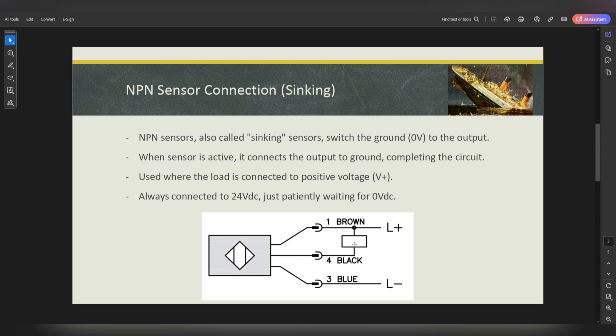When I speak about the load, it simply means the device which the sensor gives power to. The load can be any device that accepts 24 volts — or even 230 volts if the sensor can switch that. These devices can be a relay, a contactor, a valve. You can also switch on sirens or horns — for example if a sensor detects an unauthorized person inside a cell or spray booth, it can signal the horn. It can also switch on a PLC input or an alarm.